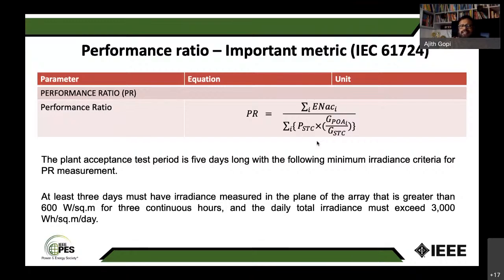If you want to compare plants internationally, any plants can be compared using PR. The quality of the plant - module quality, inverter quality, wiring quality, string combiner box quality - all of this can be well compared through this performance ratio. It's a global measure to compare a plant, rather than using generation.